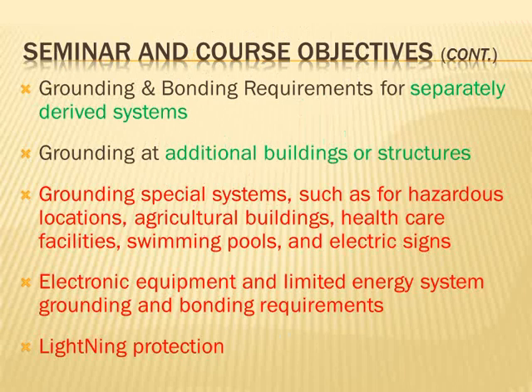And the idea behind it when it comes to electronic equipment is you want to eliminate the possibility of any ground fault or any transient in your system, because any transient in your system, regardless of how small that transient voltage or current is, could burn your server. That costs a lot of money. So grounding and bonding for electronic equipment becomes not just for the ground fault, but for the survivability of these very expensive pieces of equipment that we do.